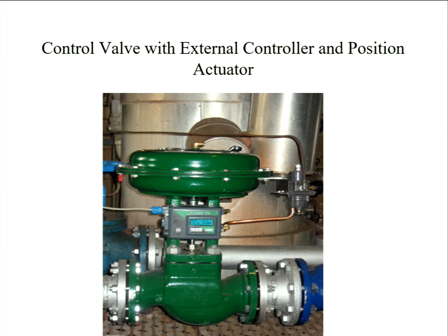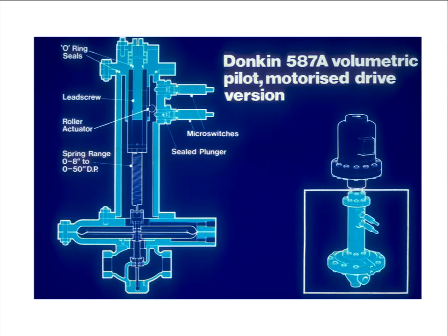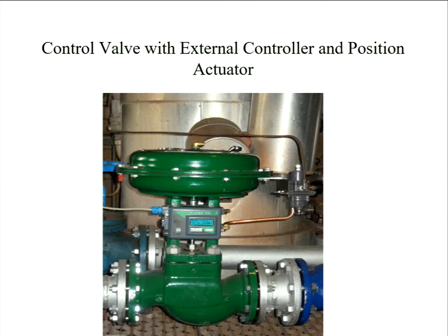These will typically only occur at the off takes where gas is taken off the national transmission system. If you wandered around Newcastle and looked at all the governor houses, you would probably never find one of those. No, it's a level of complexity that's not needed. It would be more like a simpler one. So this was a motorised drive one, again probably used more on things like gas holder stations, so perhaps not a lot of those about, certainly in the UK these days. And again, because you're in a gaseous atmosphere, this housing here had to be flame proof.